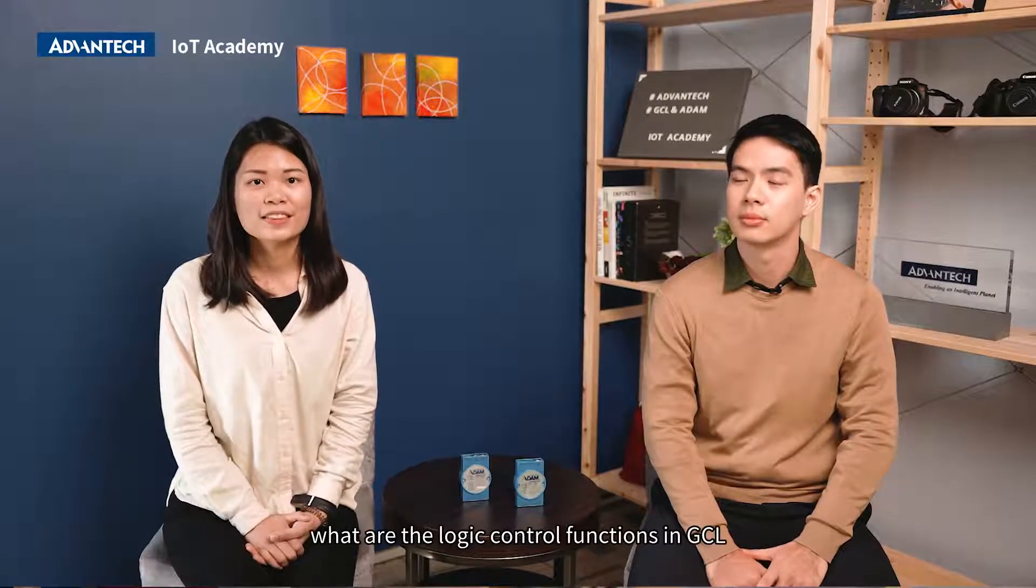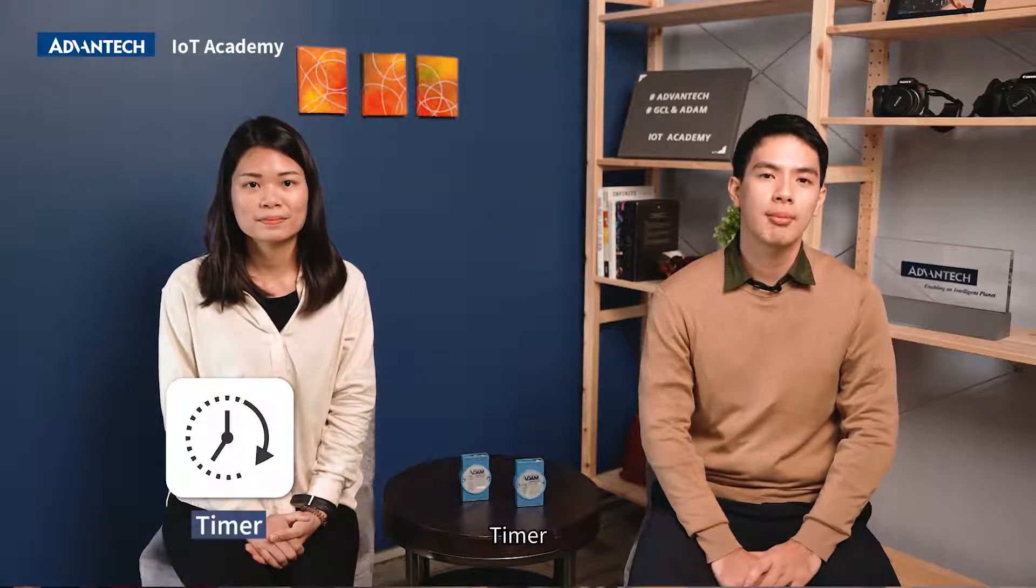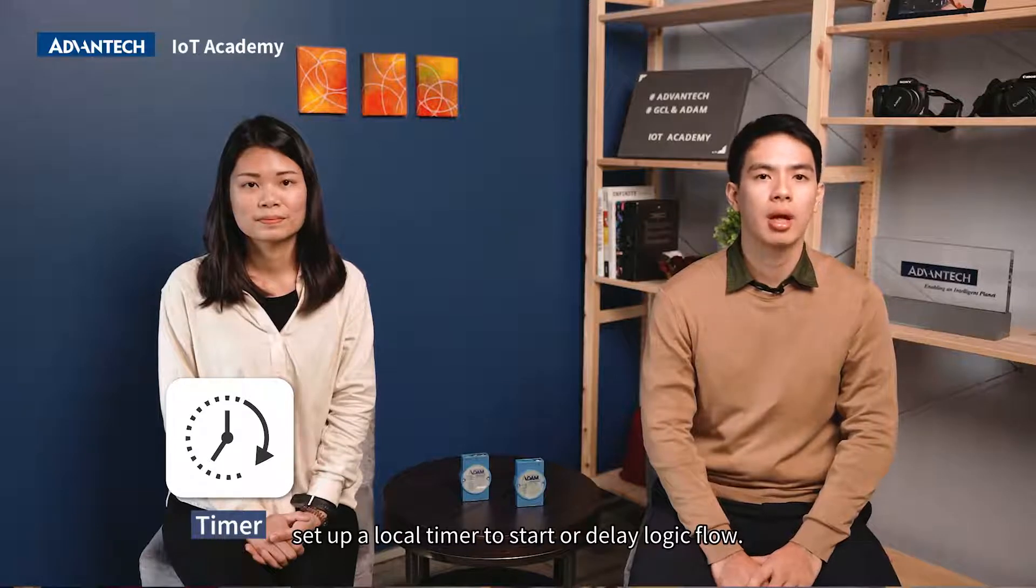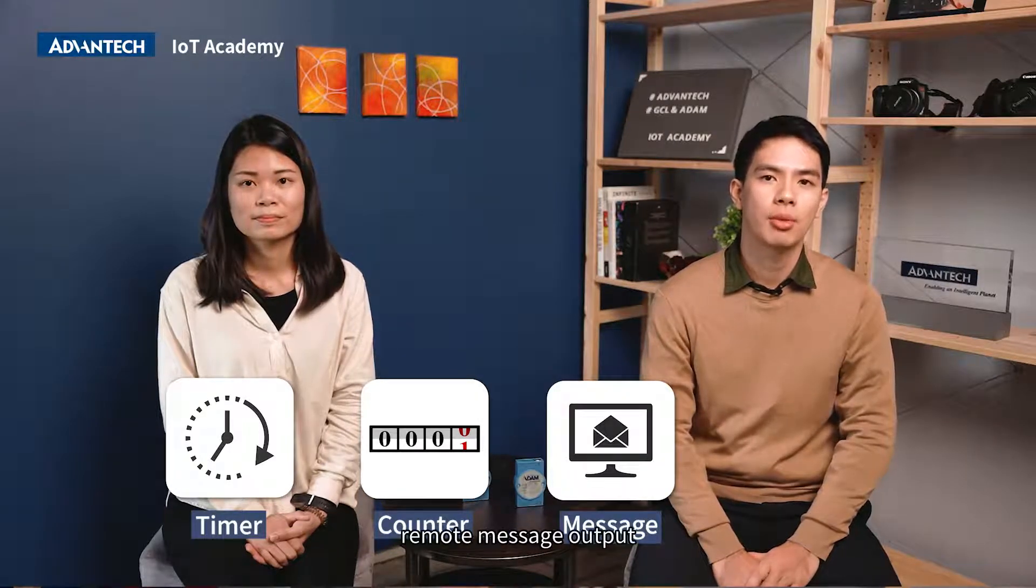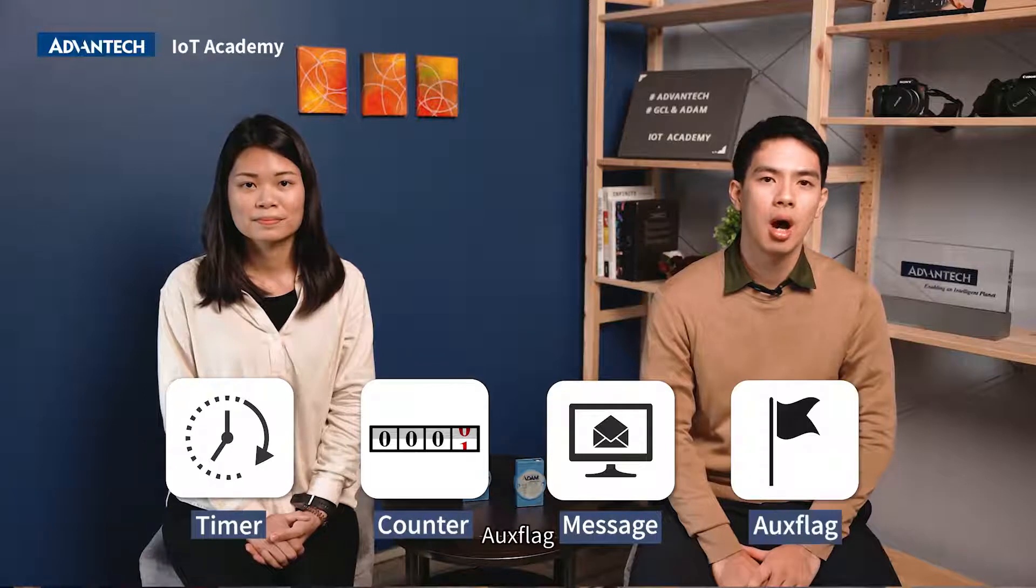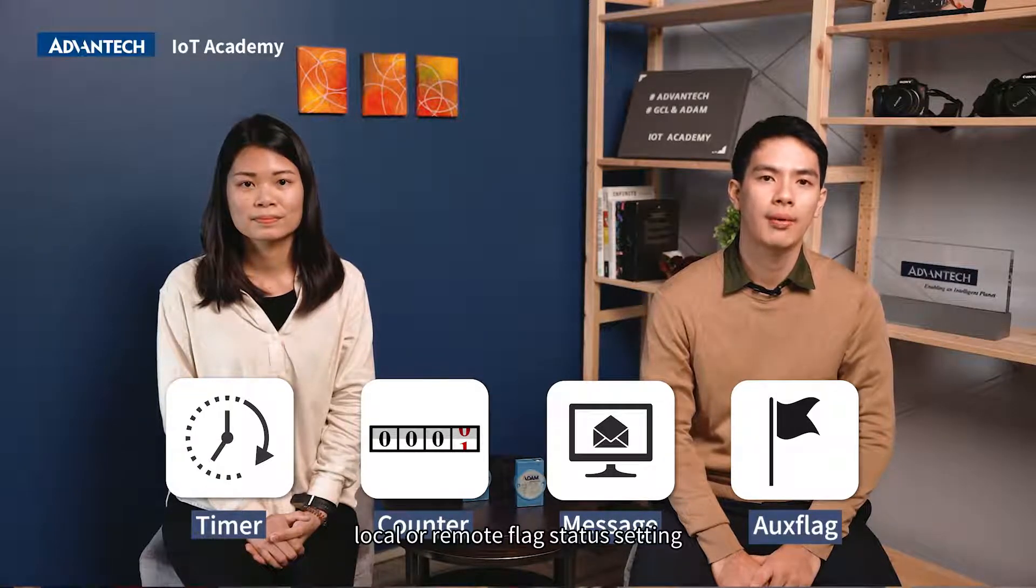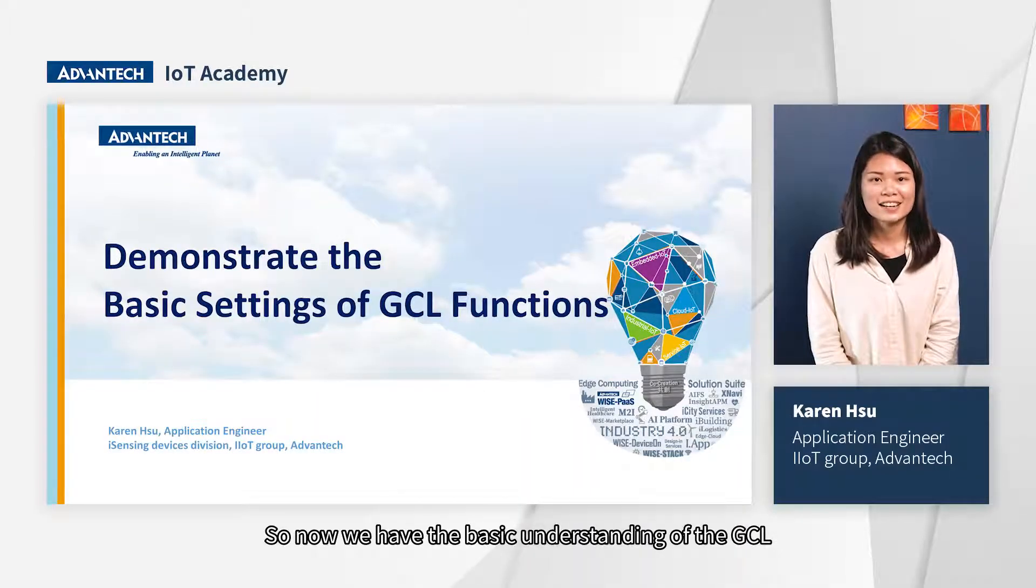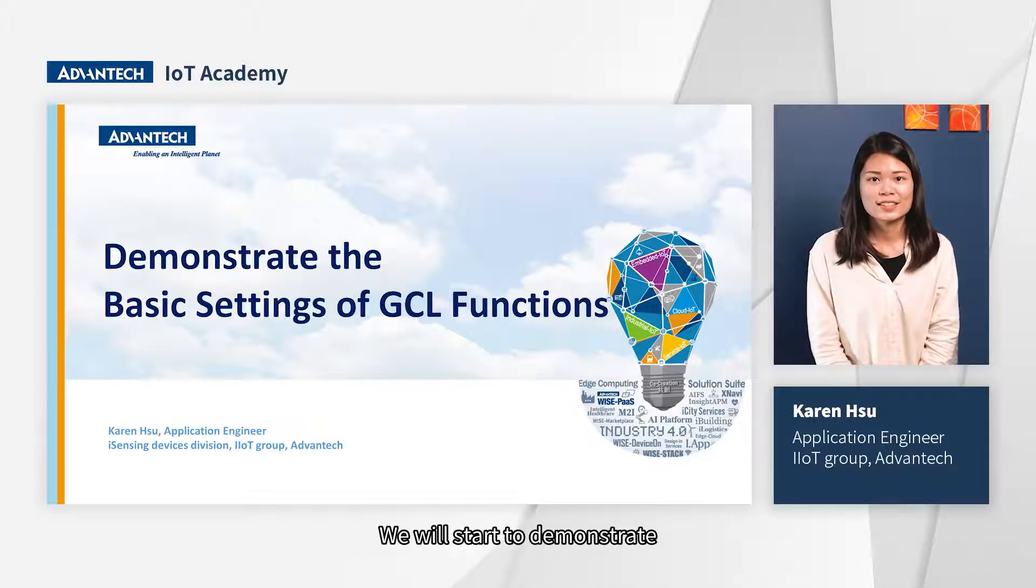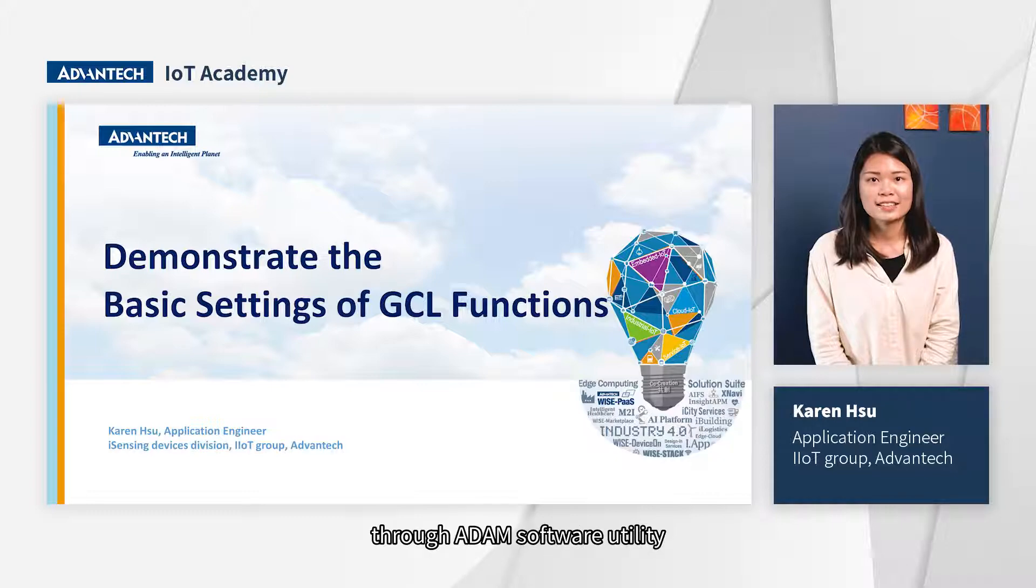It sounds like GCL function is very useful and convenient. So what are the logic control functions in GCL? There are many functions in GCL such as timer, to set up a local timer to start or delay logic flow. Counter is to count the pulse numbers of digital signal. Message means remote message output. Aux flag stands for local or remote flag status setting. So now we have the basic understanding of the GCL and the power of it. We will start to demonstrate how to set up the GCL function through ADAM software utility.